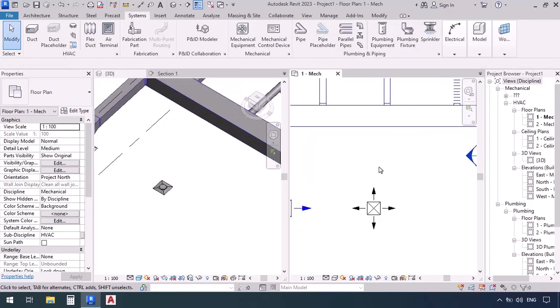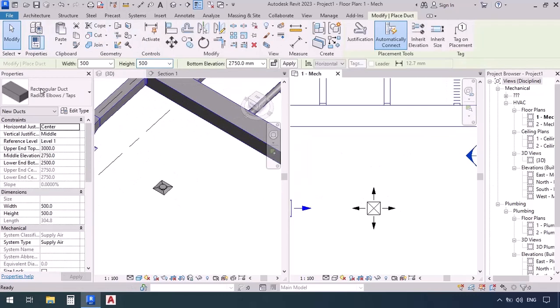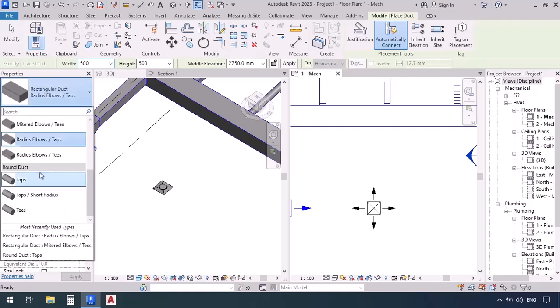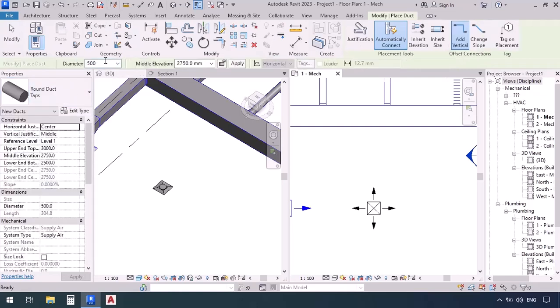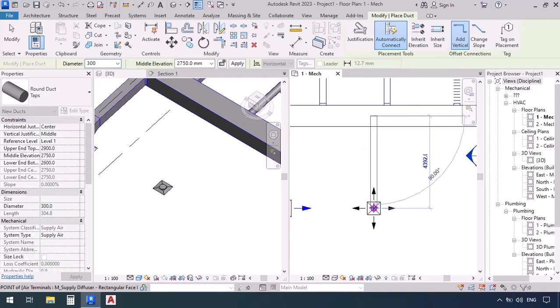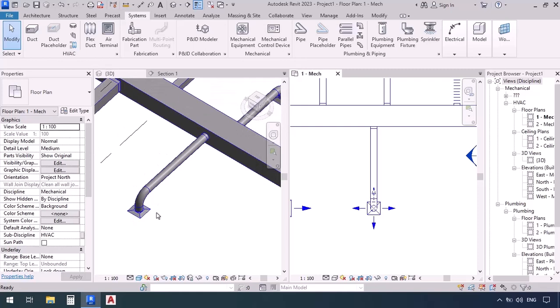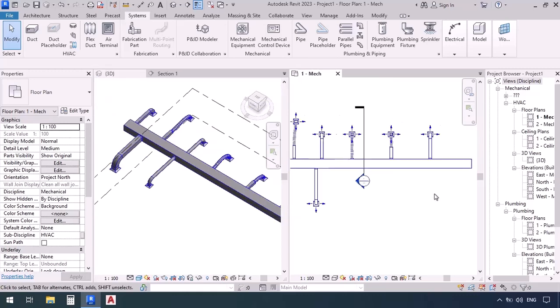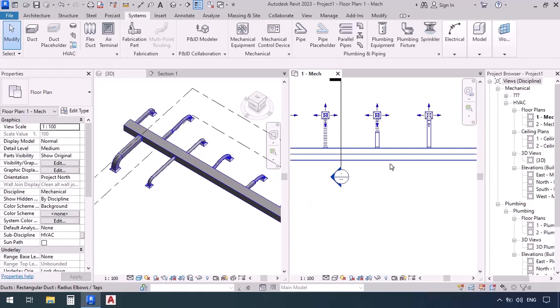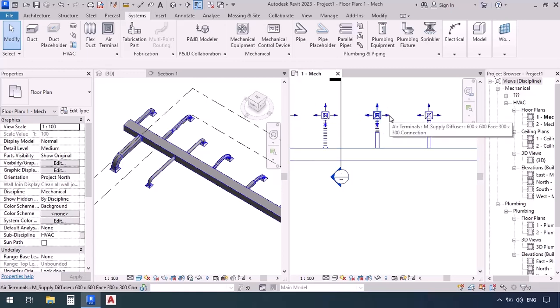Enter its elevation as 2000, go to the plan, click and place it in a proper space, then press escape. Now go to the systems tab, activate the duct command, select a round duct with diameter 300, click and click again, then escape. Our neck is round and we've drawn a circular duct — because of that Revit didn't find it necessary to apply a rectangular to round transition to make this connection happen.